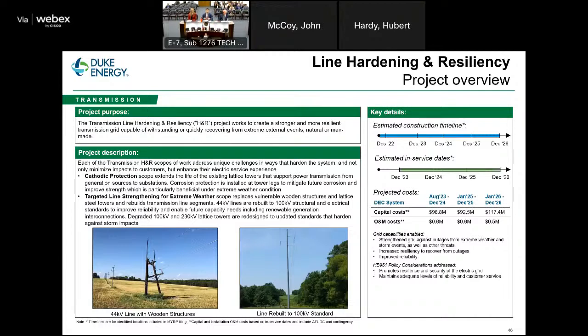Where the towers embed in the ground line is the most probable location of failure—that's where the corrosion actually starts, typically the weakest point of the tower. We're installing anodes at these locations, which arrests the corrosion, restores that tower leg back to a like-new condition, and significantly extends the life of that specific tower.